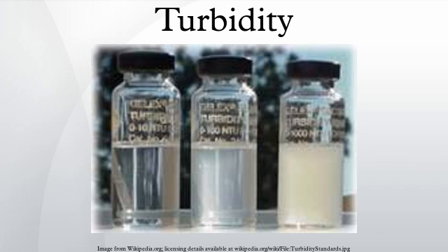Standards and test methods. Drinking water standards. Governments have set standards on the allowable turbidity in drinking water. In the United States, for systems that use conventional or direct filtration methods, turbidity cannot be higher than 1.0 nephelometric turbidity units at the plant outlet, and all samples for turbidity must be less than or equal to 0.3 NTU for at least 95% of the samples in any month.